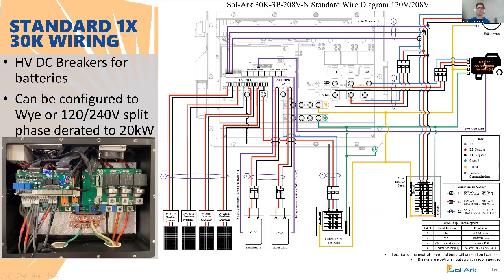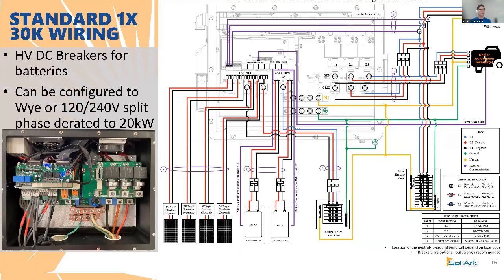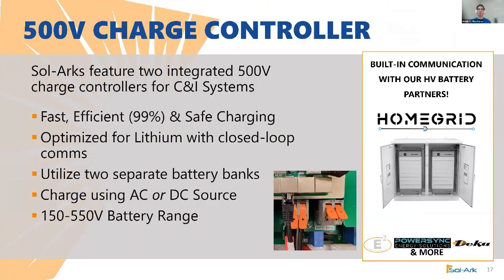PV input as well. And you have your PV input and all of your comms ports right up here, as well as some sensor inputs, so that you can ensure that your generator is connected, and you can use automatic gen start for that. And so we're going to talk a little bit about the 500 volt charge controller for the 30K, and it does feature 2 integrated 500 volt charge controllers for both of our C&I systems, which is fast, efficient, and ensures safe charging. And this one is different from the previous slide because it is optimized for lithium with closed loop communications only. I'm going to say that one more time.